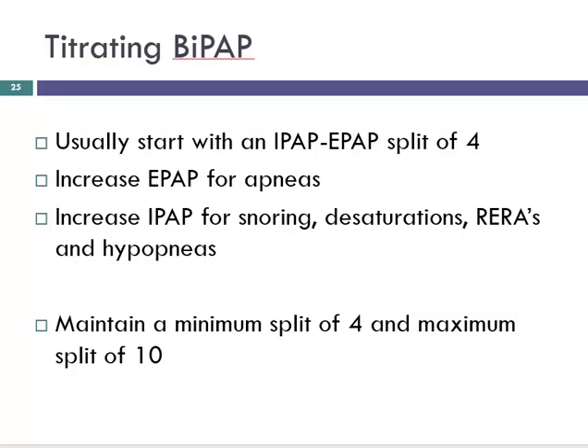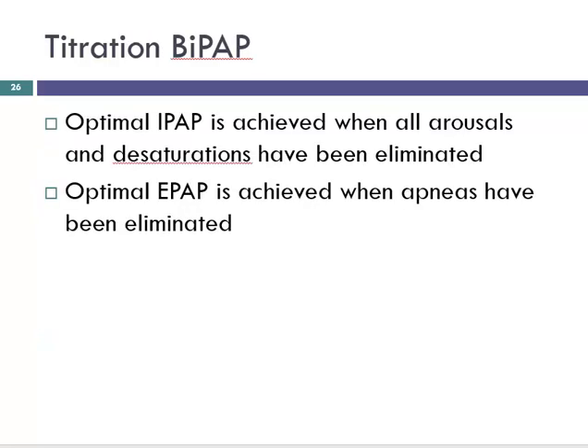Basically, these two pressures can be set independently. How you start is you have a 4 split. You keep moving them up together until you eliminate the apneas, and then you plant the EPAP there. Then you keep going up on the IPAP until you eliminate all the other respiratory events: hypopneas, RERAs, snoring, desaturation. If you hit a 10 split, meaning a 10 pressure difference between IPAP and EPAP, then you have to keep going up in a stepwise fashion again. Make sense? That's the textbook.